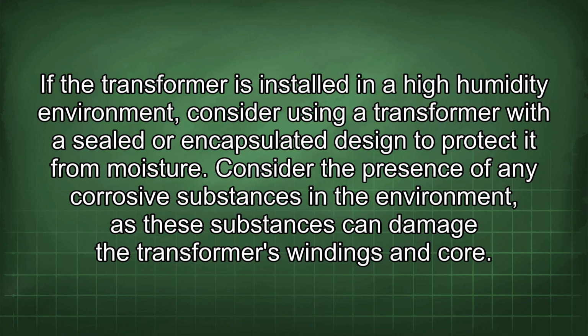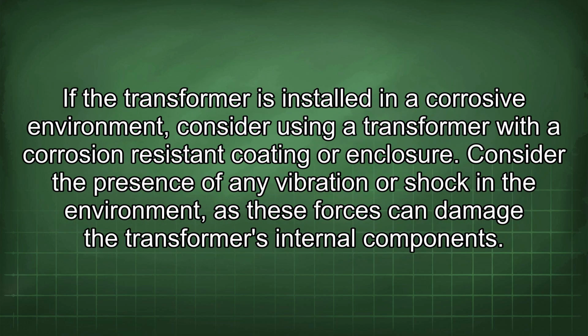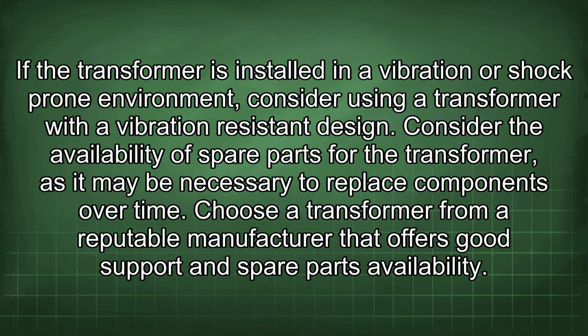Consider the presence of any corrosive substances in the environment, as these substances can damage the transformer's windings and core. If the transformer is installed in a corrosive environment, consider using a transformer with a corrosion-resistant coating or enclosure. Consider the presence of any vibration or shock in the environment, as these forces can damage the transformer's internal components. If the transformer is installed in a vibration or shock-prone environment, consider using a transformer with a vibration-resistant design.